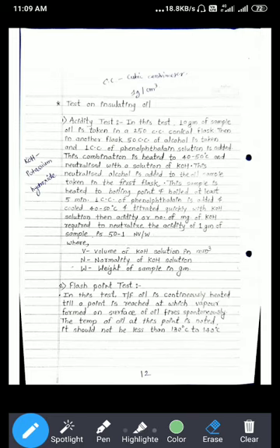The same is to be repeated here. You have to heat till the point is reached at which vapor formed on the surface of oil fires spontaneously. The temperature of oil at this point is noted. It should not be less than 130 degrees Celsius to 140 degrees Celsius. Means whatever the temperature is, the minimum range is 130 to 140 degrees Celsius for the flash point test. This is the minimum requirement.